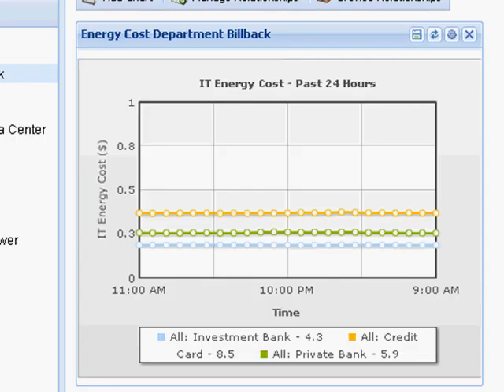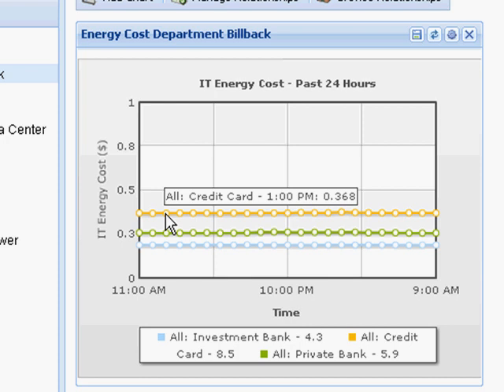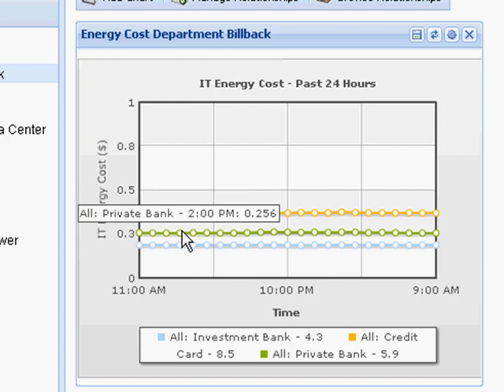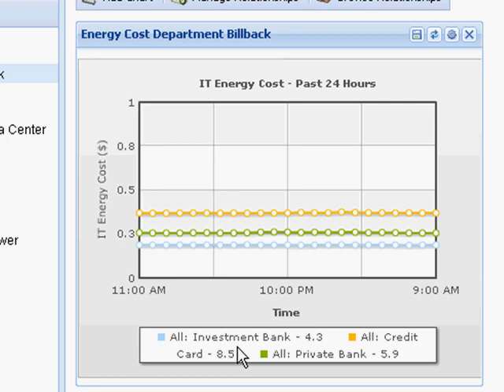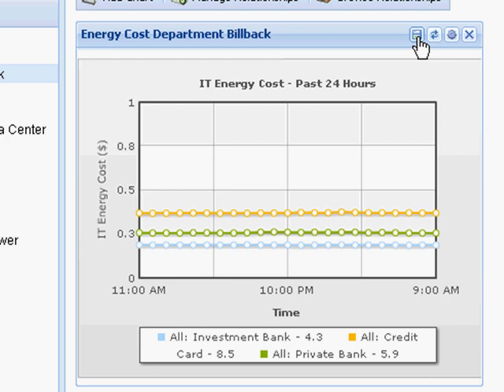Another chart is my department energy cost billback report. In this particular case, I'm graphing IT energy cost in dollars. You can enter your own local currency, including pound, yen, or euro, as well as a number of other currencies. I'm showing the trend line in terms of energy cost for my credit card division, my private bank division, and my investment bank division. The window below gives the cumulative total cost in dollars over the graphed period, which in this case is the past 24 hours. I have the ability to export this data by merely clicking the export widget, and this will export the data into a CSV file which can easily be manipulated in Excel.